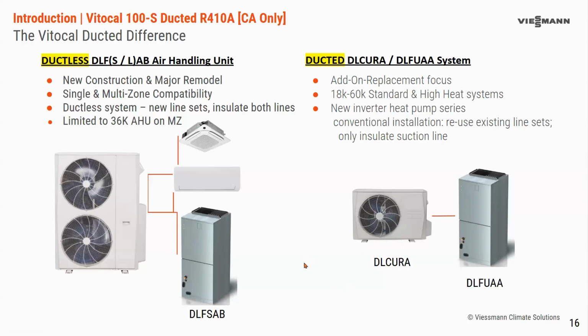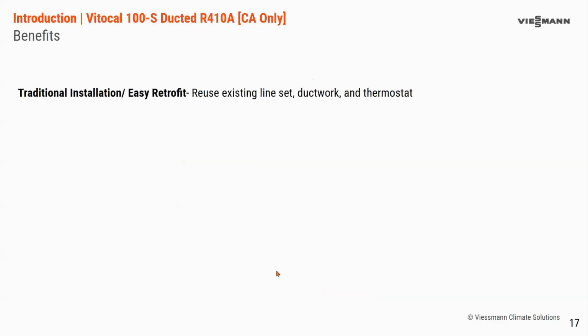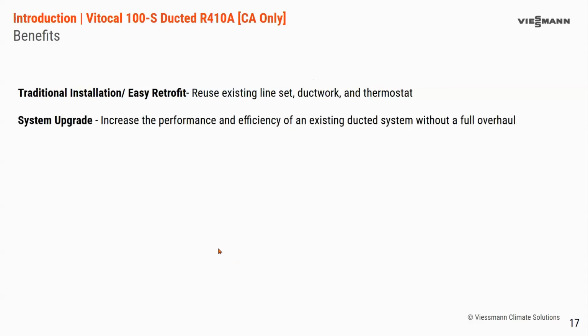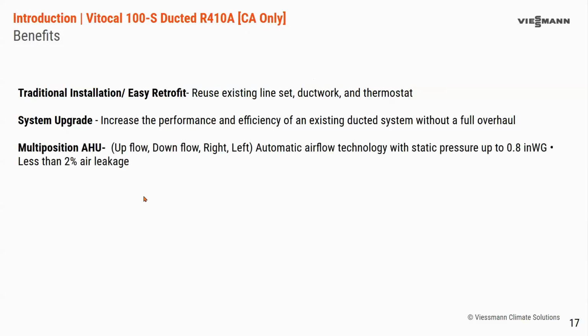So really, if you want to mix, or you're doing a hybrid system, the ductless air handler may be the right choice. But if you're strictly focusing on central ducted, then the ducted system would be the best. So benefits of this ducted system: traditional installation, easy to retrofit. You can upgrade an existing system without a full overhaul. We have the air handler indoor unit available that'll either replace a fan coil or replace a furnace, and it has the automatic airflow technology, four-way multi-position cabinet, and the tight less than 2% air leakage.